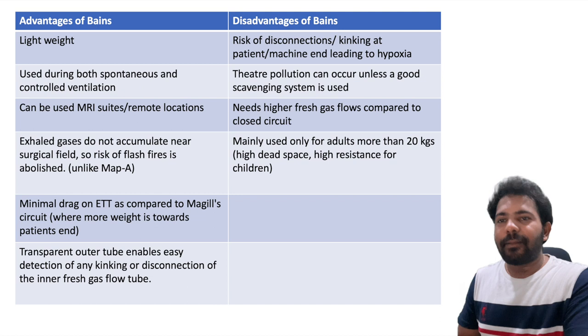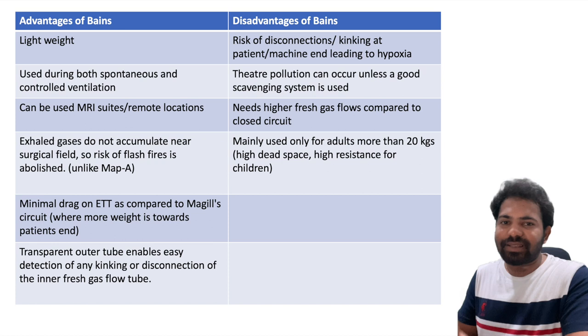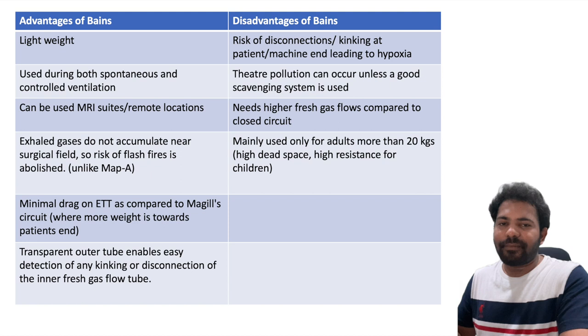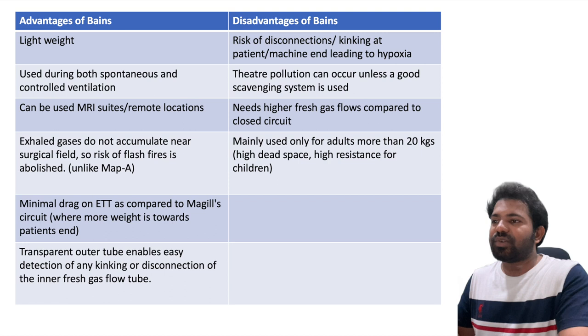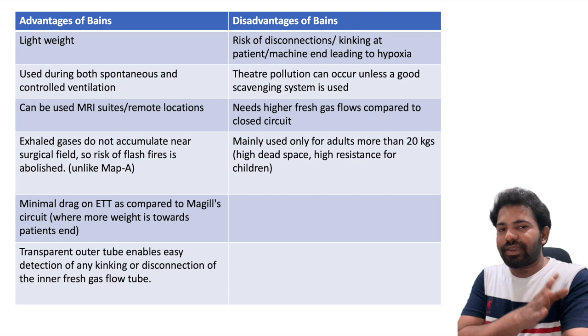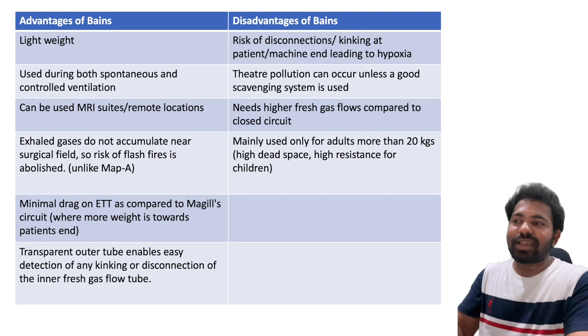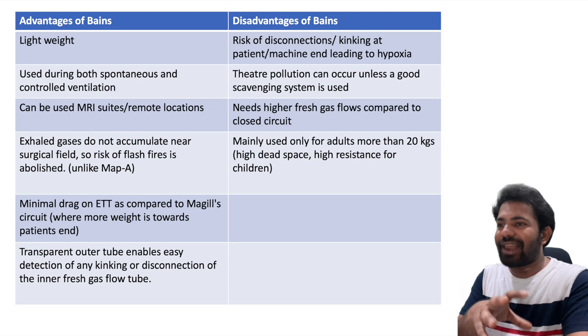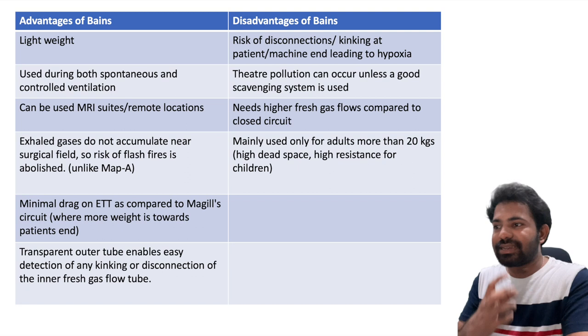Advantages of the Bain circuit include: it is lightweight, portable, and transparent; it can be used during both spontaneous and controlled ventilation; it can be used at remote locations such as MRI and angiography suites; exhaled gases do not accumulate near the surgical field, abolishing the risk of flash fires (unlike Mapleson A, where the APL valve near the patient's end can allow combustible gases); minimal drag on the ET tube; and the transparent outer tube enables easy detection of kinking or disconnection of the inner fresh gas flow tube.